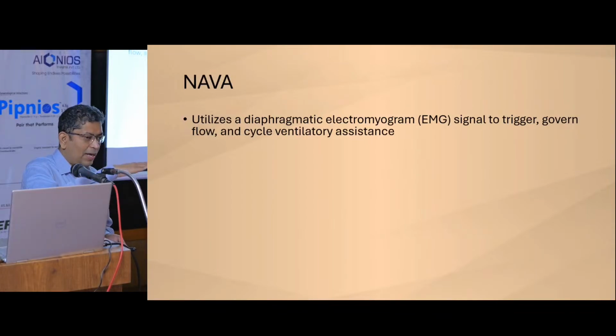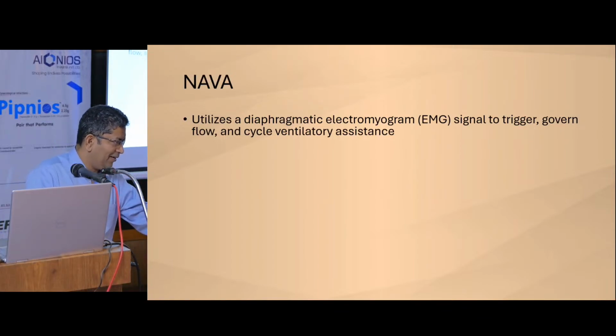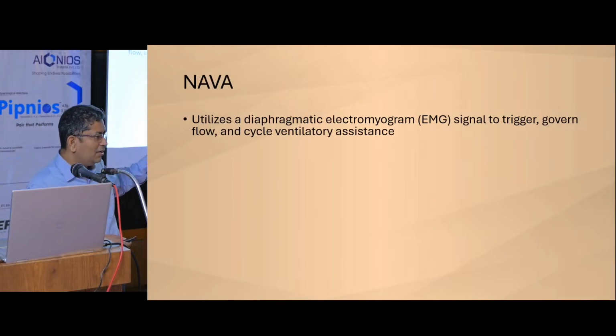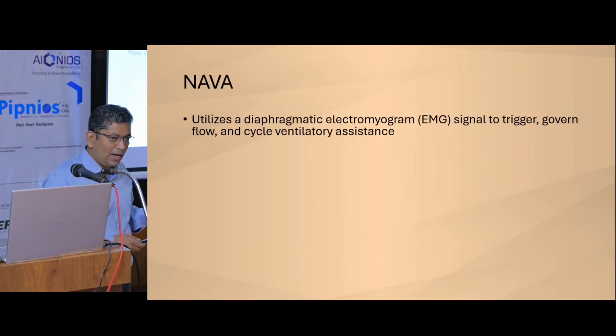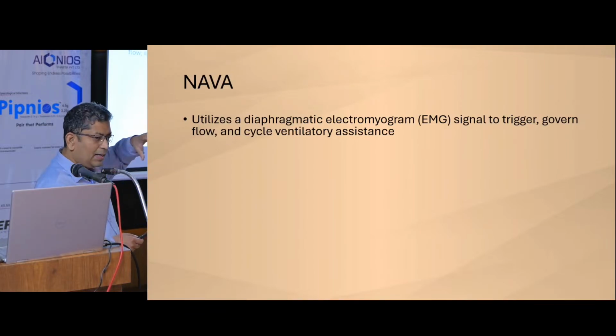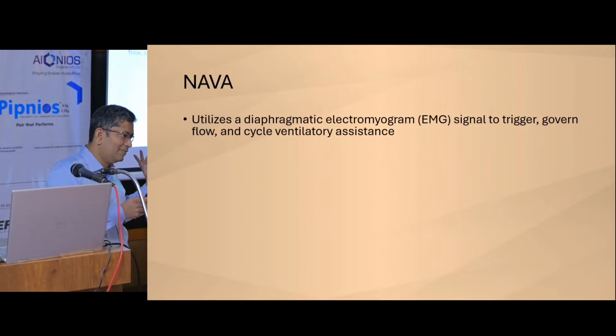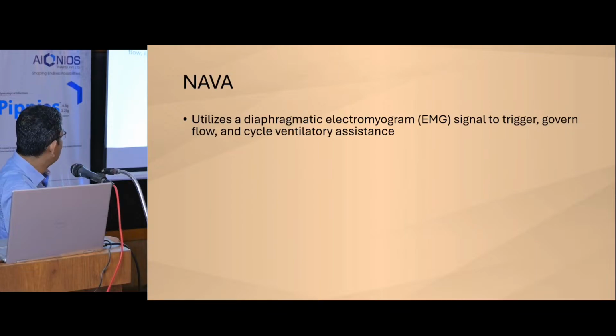The ventilator knows how much electricity is produced. If you want to breathe more, you produce more electricity, and accordingly the ventilator will increase or decrease the pressure support. If you breathe less, then less support. And the moment you stop breathing, the electricity disappears. So the trigger, limit and cycling can all depend on the electrical signals from the diaphragm, not on anything else. Got it? So that's what we do with this.